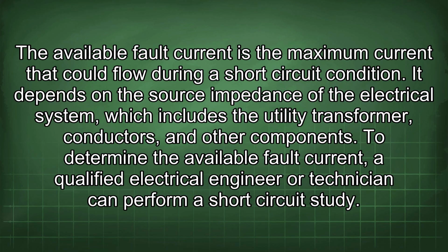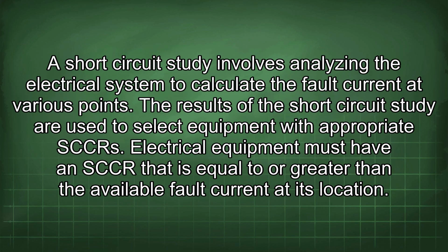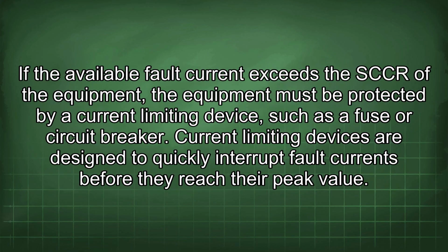It depends on the source impedance of the electrical system, which includes the utility transformer, conductors, and other components. To determine the available fault current, a qualified electrical engineer or technician can perform a short-circuit study. A short-circuit study involves analyzing the electrical system to calculate the fault current at various points. The results of the short-circuit study are used to select equipment with appropriate SCCRs. The electrical equipment must have an SCCR that is equal to or greater than the available fault current at its location. If the available fault current exceeds the SCCR, the equipment must be protected by a current limiting device such as a fuse or circuit breaker.